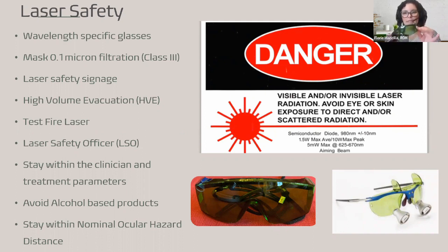These are very specific to the wavelength of your laser, and they're usually marked on the left side of the glass, so you can see what wavelength they cover. It is recommended that you use a class 3 filtration mask, and you have signs that get put up and then taken down when the laser is not in use.